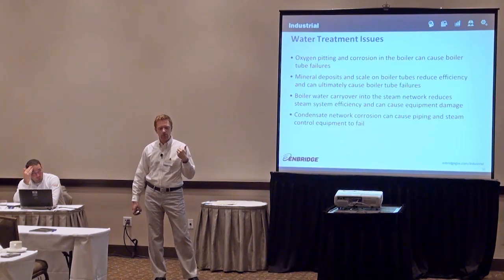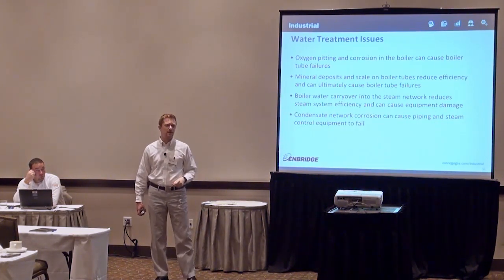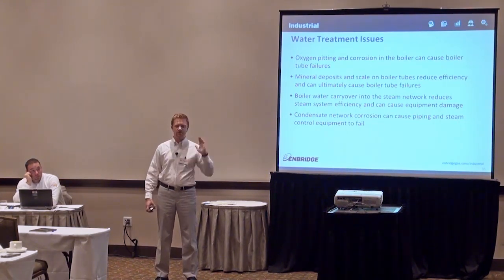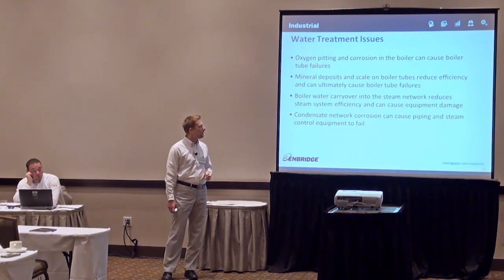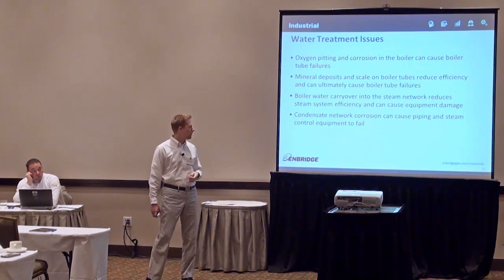And there's a whole bunch of negatives that come along with that. One is you've got droplets of water moving at very high rates, because steam moves fast through a pipe. We've now got water going through that pipe with it. And if there's a bend in that pipe somewhere at an elbow, that water hits that elbow at a really high rate and actually has an abrasive effect and can eat through your elbow. It can cause all sorts of problems with steam control, pressure control equipment, and whatnot.